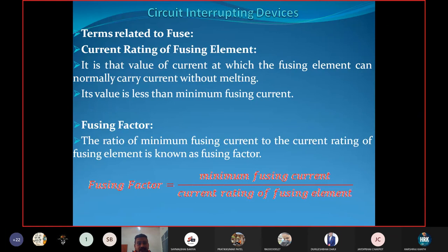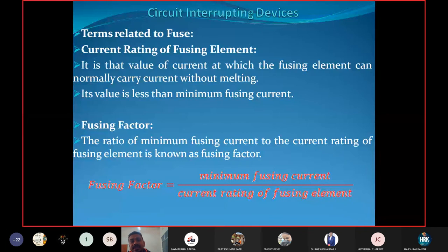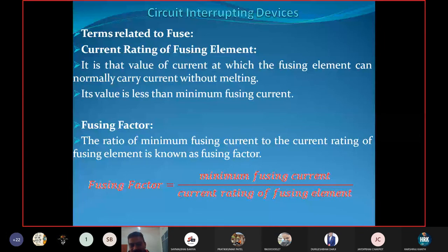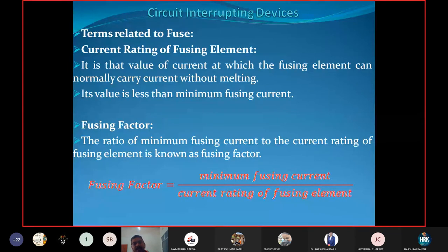The current rating of the fusing element is the value of current at which the fusing element can normally carry current without melting. For example, if current rating is 6 amperes, up to 6 A the element carries current safely, but above 6 A it will melt. The current rating is always less than the minimum fusing current.